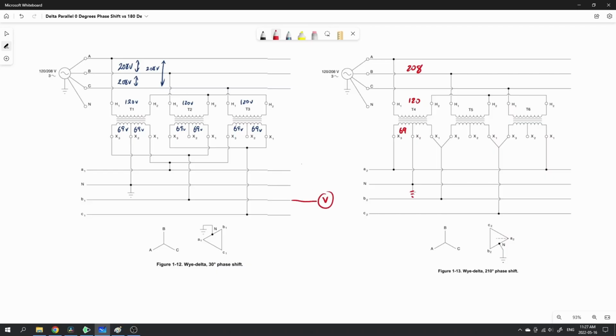So this voltage right here - again, common connection on the neutral. We're coming along this bus, coming up to here, and it looks like that connection goes to the first transformer, because that first transformer is going from A to B.